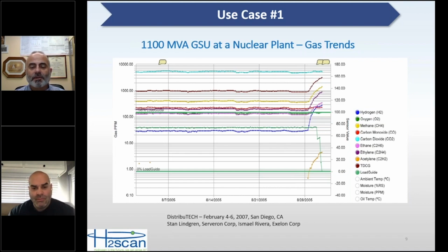If you look at the hydrogen value here, it's hard to see on the scale, but you can trust me that the hydrogen value went from about 30 ppm to almost 300 ppm in 2 days. The primary reason for that is that acetylene started being generated. Acetylene pops in at about half a part per million on the chart there, and over 2 days gets up to about 4.5 parts per million. So when we generated just a little bit of acetylene, we generated lots of hydrogen. At that same time there was also overheating, and in that 2-day period there were significant amounts of other gases, your methane, ethane, and ethylene, going up. But if this transformer had only had a hydrogen monitor on it, you would have seen about a 10-fold hydrogen increase in 2 days, from about 30 to about 300.